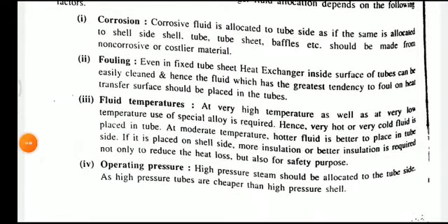The other parameter is fouling. Even in a fixed tube sheet heat exchanger, the inside surface of the tubes can be easily cleaned, and hence the fluid which has the greatest tendency to foul the heat transfer surface should be placed in the tubes.